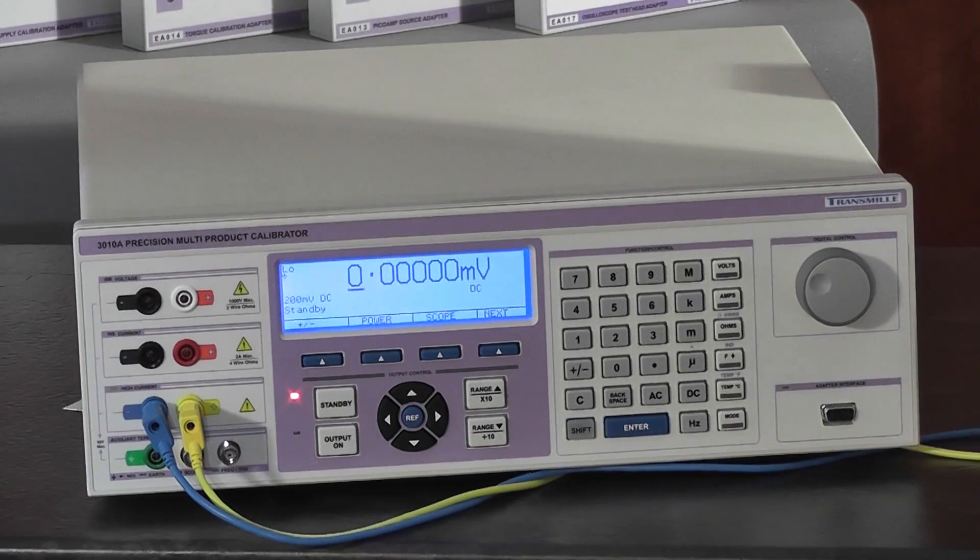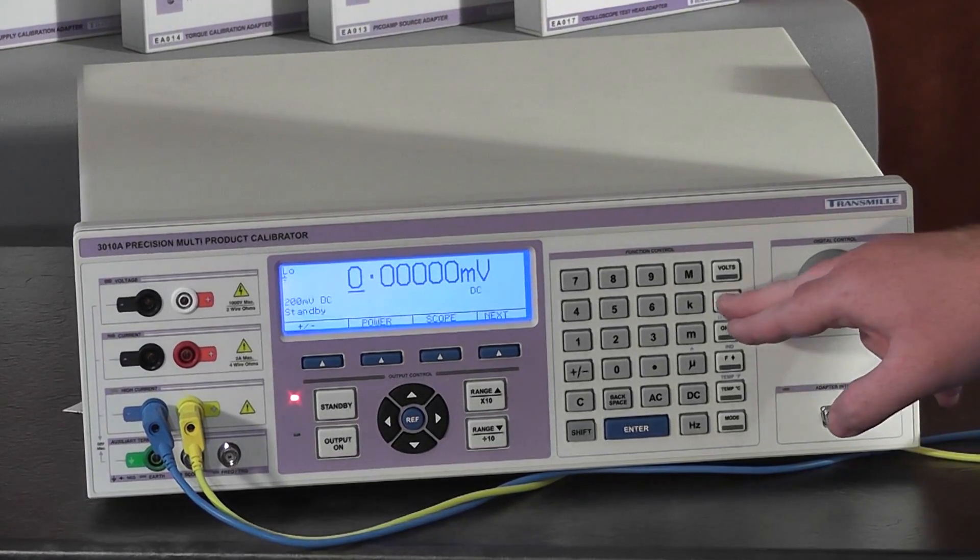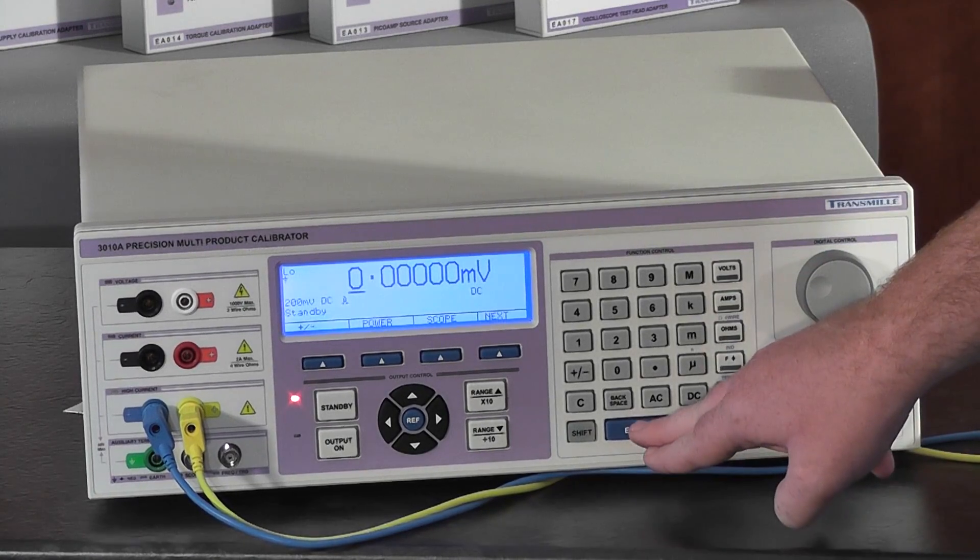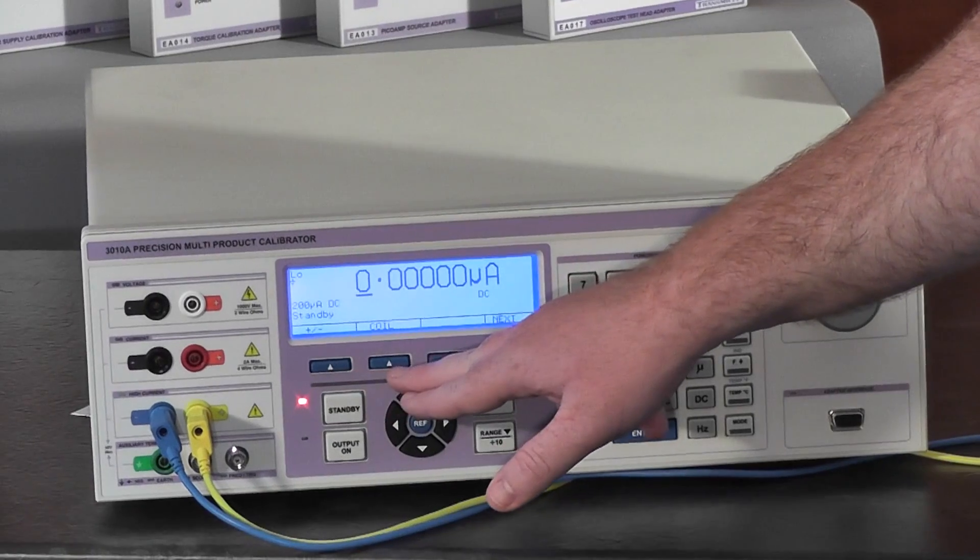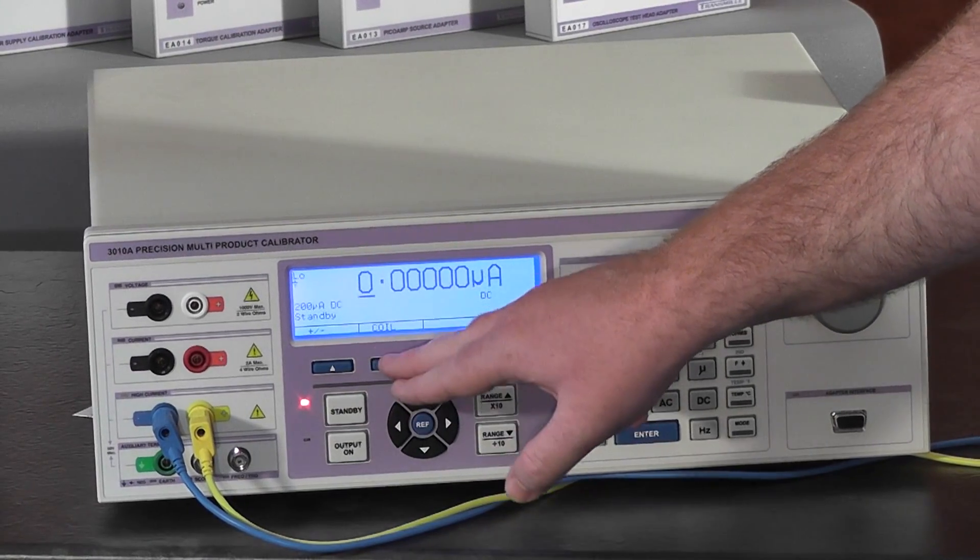To set the calibrator, first enter the current mode by selecting amps and pressing enter. As we're using a coil we want to use the coil mode, so we press coil.